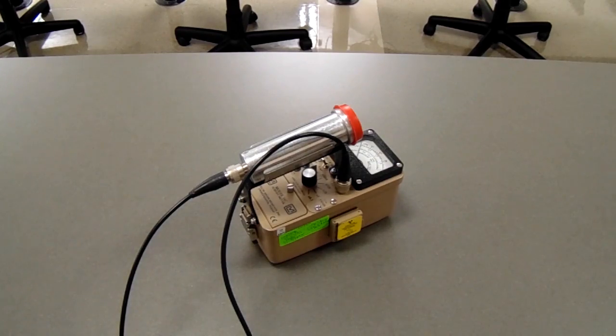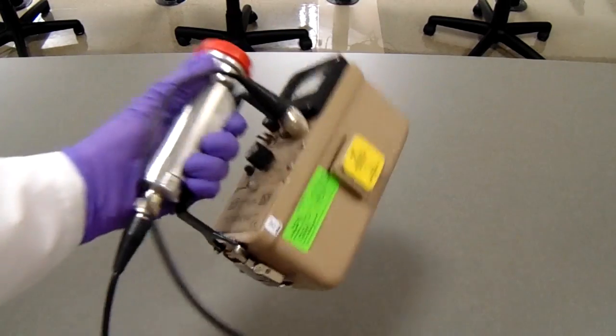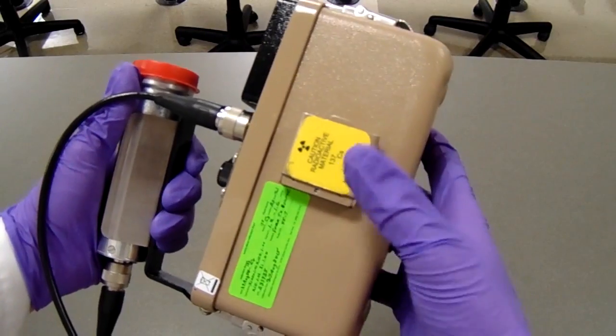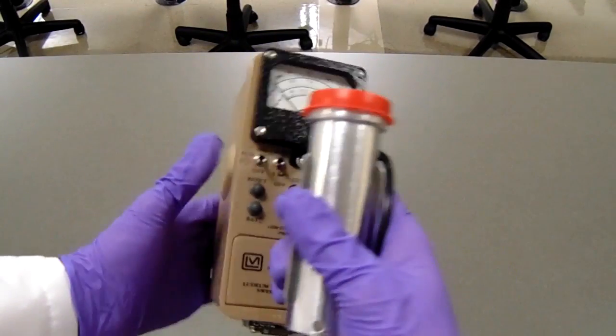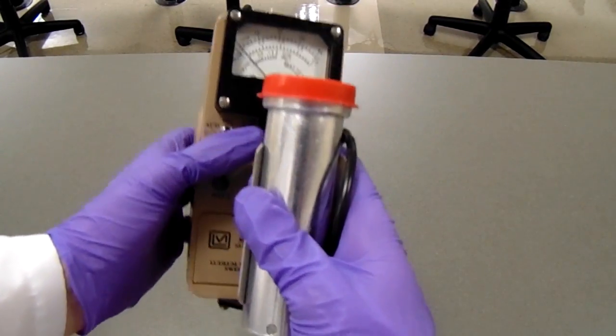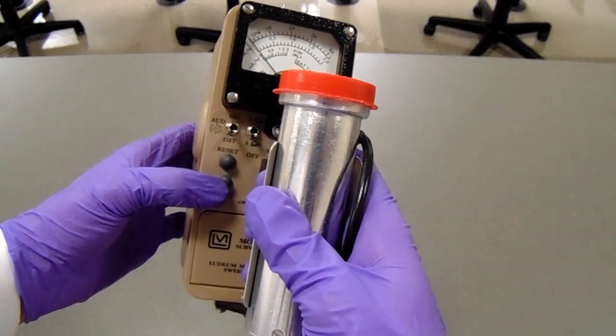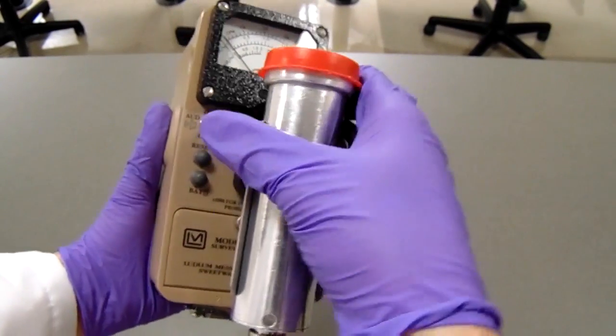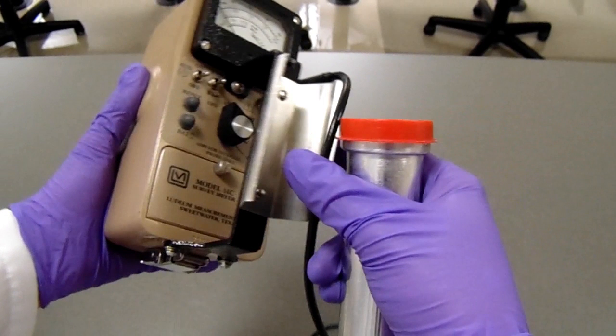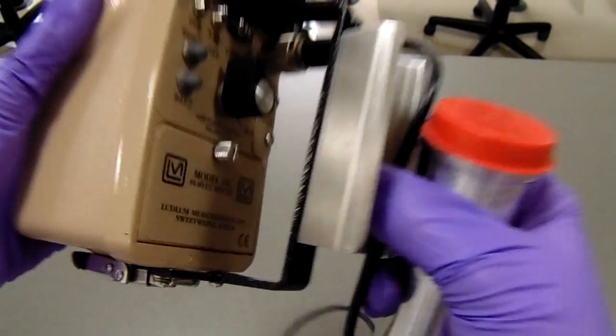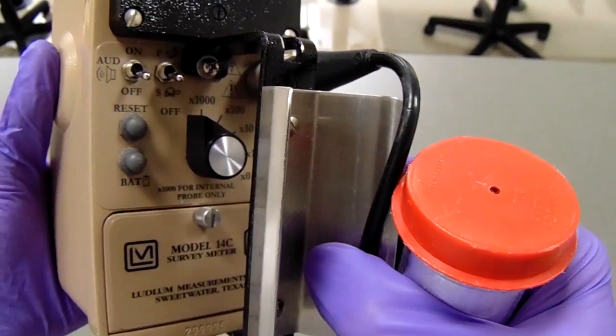So first thing we're going to go over is our GM meter and the constancy of it. First, you're probably going to want to start out talking about the physical appearance of the GM meter. You've got your cesium 137 source there on the side under the garage door. You've got your volume on and off switches, your fast and slow detector speed switch, your battery test button, and your reset button. Right here you'll probably want to talk about the probe and how it's filled with inert gas that ionizes the radiation and turns it into a voltage, which the meter reads out.